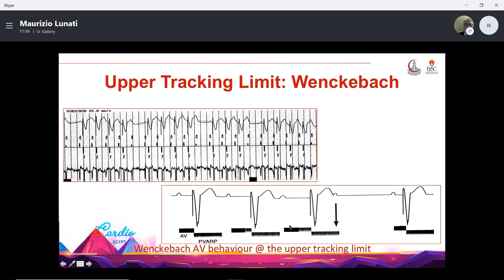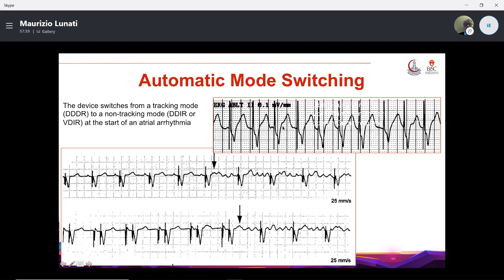One of my last slides. What is automatic mode switching? If a patient during his life has a relapse of atrial fibrillation and we don't want the patient to have a high rate due to this atrial arrhythmia, the device switches from a tracking mode, DDD, to a non-tracking mode, DDI, at the start of an atrial arrhythmia. If automatic mode switching was not on, obviously the patient could have this heart rate instead of this, and this could be really bad for him.